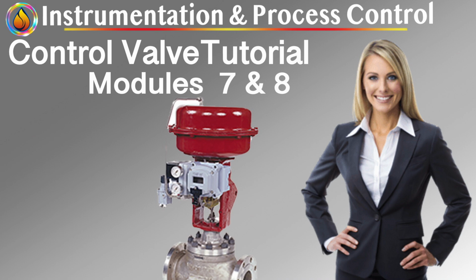Purpose of positioners. A positioner's fundamental job is simple in concept and profound in impact. Ensure valve position accurately follows controller output, quickly, repeatably, and independently of disturbances. Accuracy versus responsiveness. Accuracy and responsiveness are related, but not identical. Accuracy: how closely actual valve position matches demanded position, dominated by calibration, feedback mechanism, and friction, determines steady-state control error. Responsiveness: how fast the valve reaches the demanded position, dominated by air capacity, internal gain, and damping, determines dynamic control quality. A valve can be accurate but slow, or fast but inaccurate.